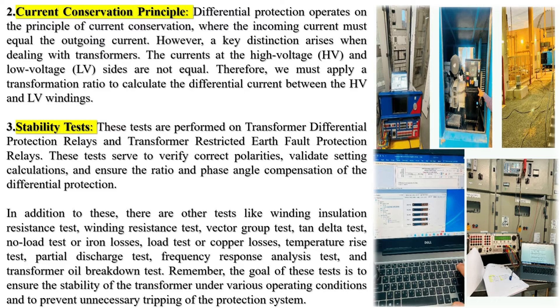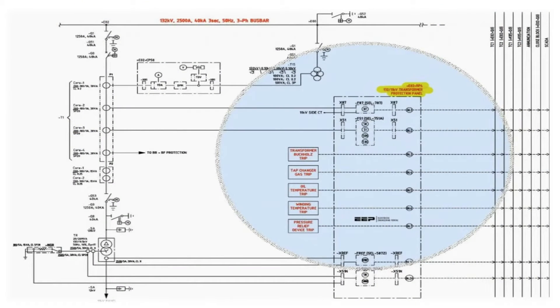Transformer Differential Protection is one of the primary methods for electrically safeguarding transformers. It operates as a unit protection scheme, meaning it responds only if the fault occurs within its designated protection zone. If the fault lies outside this zone, the differential protection should not trigger.